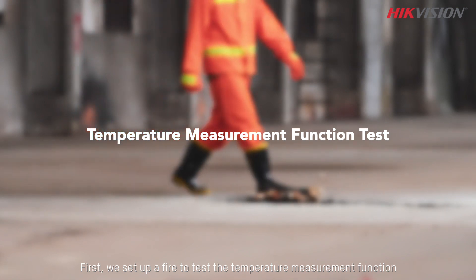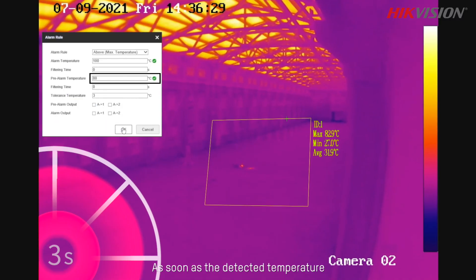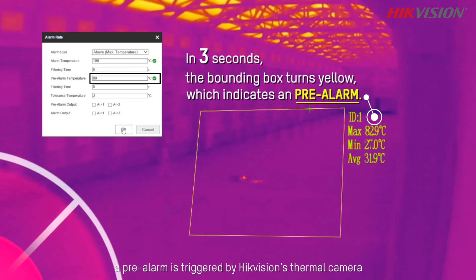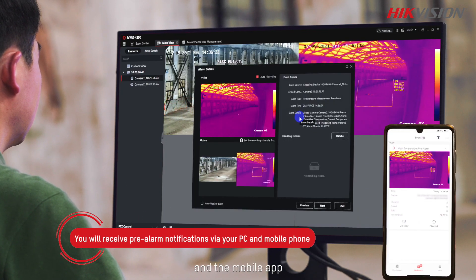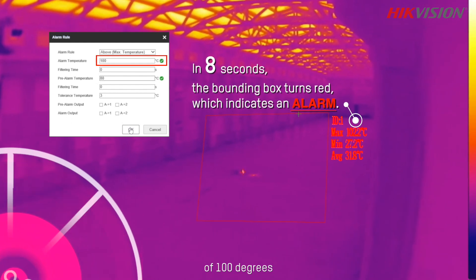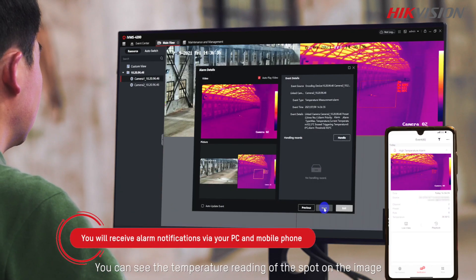First, we set up a fire to test the temperature measurement function. As soon as the detected temperature reaches the preset 80-degree threshold, a pre-alarm is triggered by the Hikvision thermal camera. A real-time image of the spot is pushed to the PC client and the mobile app. Once the temperature reaches the next threshold of 100 degrees, a formal alarm is given by the thermal camera. You can see the temperature reading of the spot on the image.